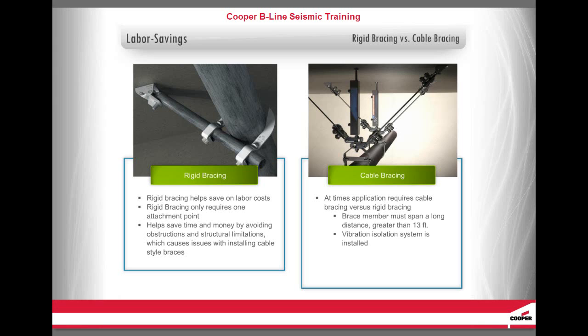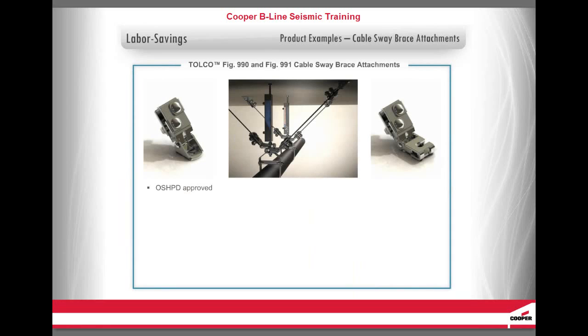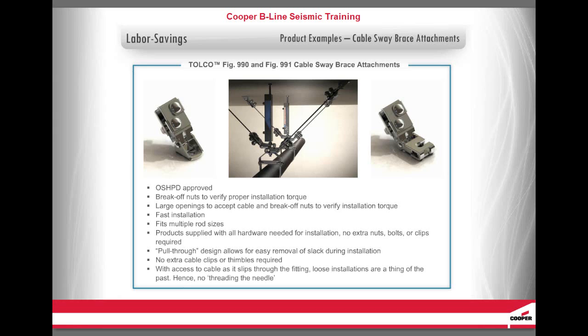Rigid bracing becomes difficult and costly in these rare cases. In such cases, Cooper B-Line offers TOLCO cable bracing solutions that can help save time and labor over the competition's similar options. The TOLCO Figure 990 and Figure 991 cable sway brace attachments are OSHPD approved and have break-off nuts to verify proper installation torque. With large openings to accept the cable and break-off nuts to verify installation torque, it's one of the fastest installations available for cable bracing. It has multi-sized rod attachments and all components are supplied with the attachments. Its pull-through design allows for easy removal of slack during installation — no extra cable clips or thimbles required. With access to the cable as it slips through the fitting, loose installations are a thing of the past, hence no threading the needle.